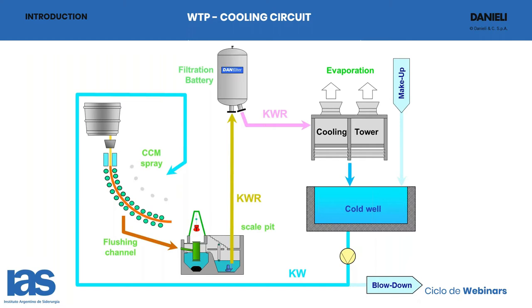The cooling tower works by spraying water on the top, which flows down just like a shower. There is air driven by fans going from the bottom of the tower to the top. With this exchange, it is possible to remove the heat load. The main part of the heat load is removed by evaporation. This means that the water circulating inside the cooling circuit is progressively reduced — at some point you will need to insert makeup water to reintegrate what has evaporated.